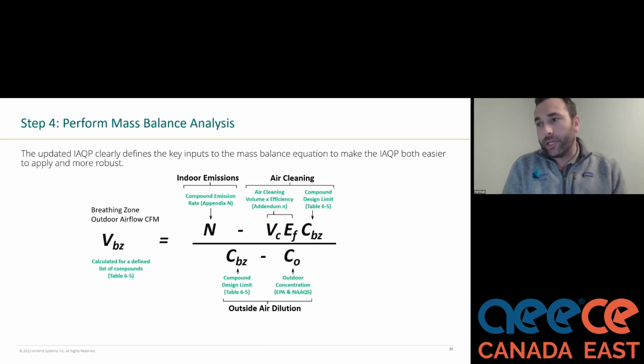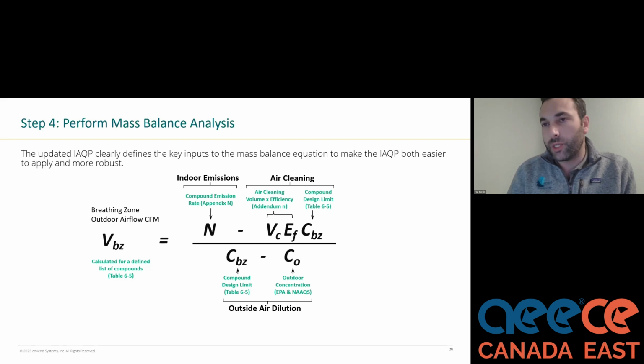Now, what is the IAQp really? And I don't want to belabor this too much because now we have an ASHRAE calculator, so we don't need to think about it too much. But realistically, what the IAQp does, different from the ventilation rate procedure, is it really hones in on ensuring acceptable indoor air quality and not just throwing a bunch of potentially contaminated outside air at the problem. And so what all of this does within the ASHRAE 62.1 is we have our indoor emission rates of each individual contaminant and design compounds. We apply an air cleaning efficiency based on the volume of air that's being treated by that device. And then we also get credit for that remaining outside air dilution, which is being done to maintain building pressurization. So that really kind of summarizes this calculation here for this mass balance equation.